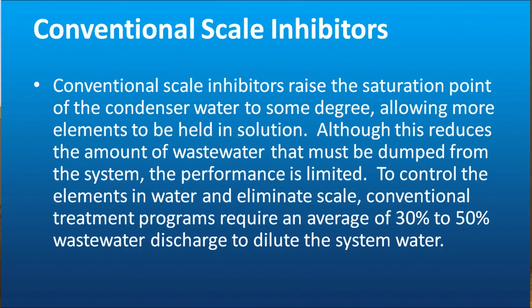So I understand some of the frustration in the room about cooling towers. In order to control the elements in the water and eliminate scale, conventional treatment programs require an average of 30 to 50% wastewater discharge to dilute the system and maintain complete system integrity.